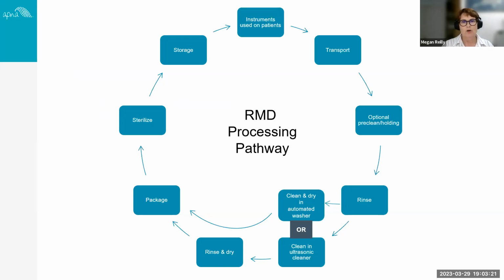So this slide is really just showing you what the RMD process pathway is if you are selecting to reprocess your devices on site. And we can see up the top of the slide that we use our RMD on the patient at the point of use. There is a process of transporting that safely through to an area where we may need to hold. If we haven't pre-treated at the treatment site, and we've got appropriate timing, we can rinse or pre-treat in the reprocessing area. We then go through the process of cleaning our instruments, whether that's manual cleaning, which is accepted under the standard currently, or some form of mechanical cleaning through an ultrasonic cleaner or an automated washer disinfector. We then rinse and dry, package, and sterilize our instruments if they're semi-critical or critical, and then they go into storage ready to be used on the next patient.